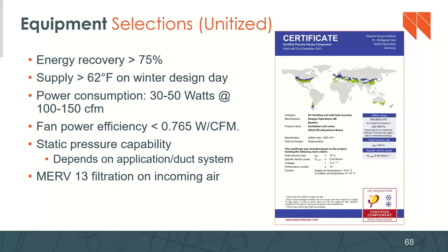And then the static pressure capability is going to depend on the system, for this box, for your ERV, HRV. What are those engineering specs? What is the static pressure that it can deal with? And this is going to be driven by your duct design. And then we also want to look for this MERV 13 filtration on the incoming air. So usually, costing for a unitized system with these specs, we've seen $800 to $1,000 per box.